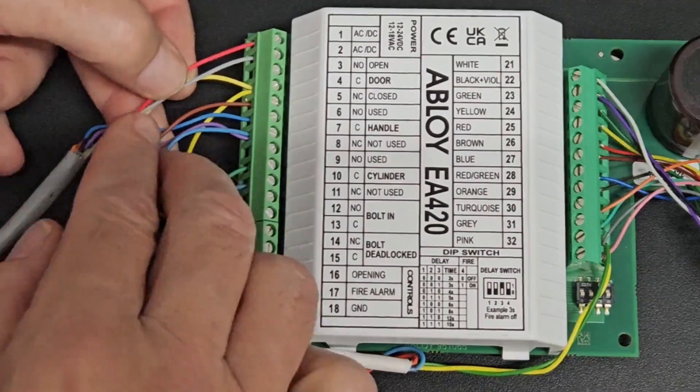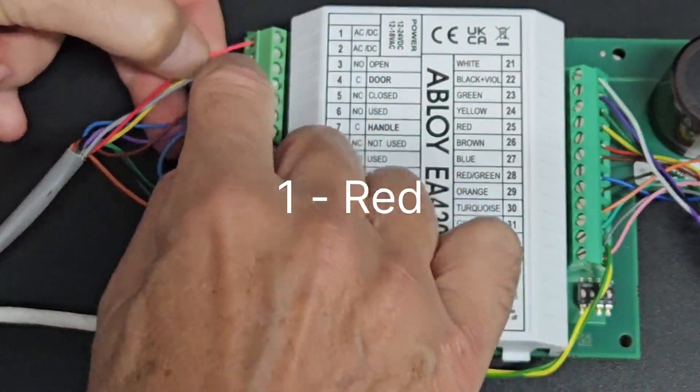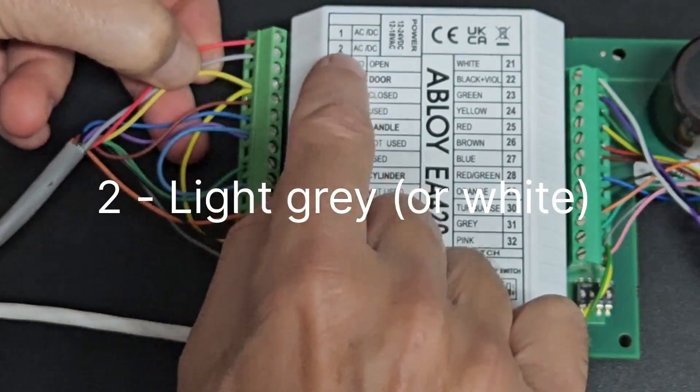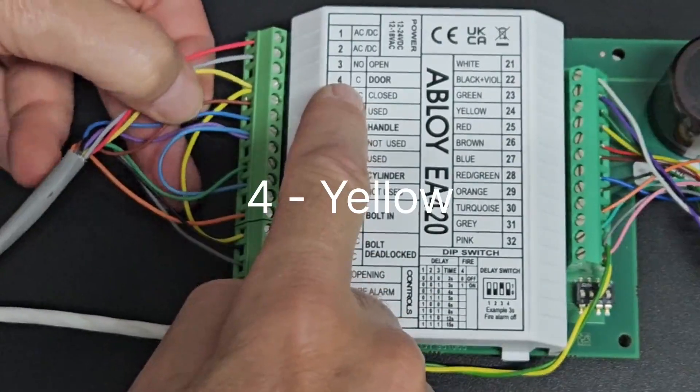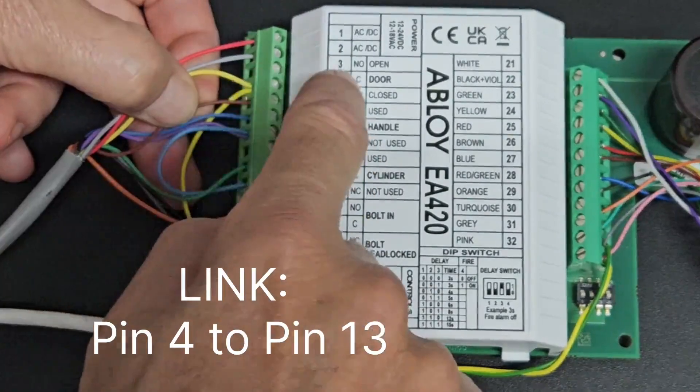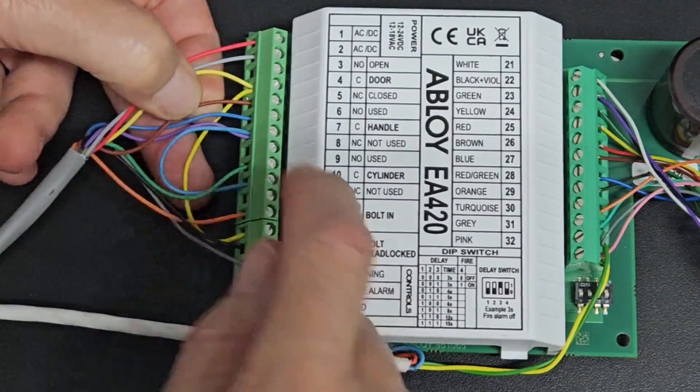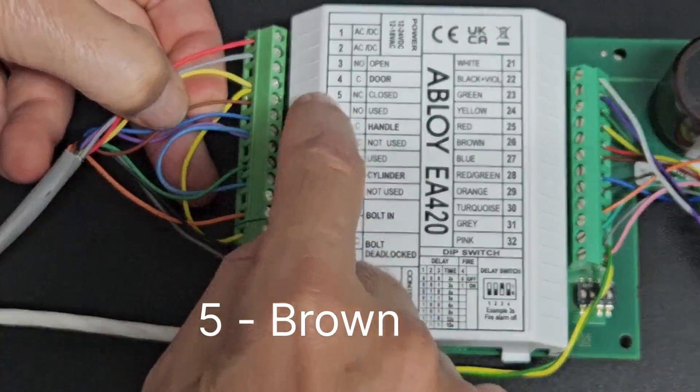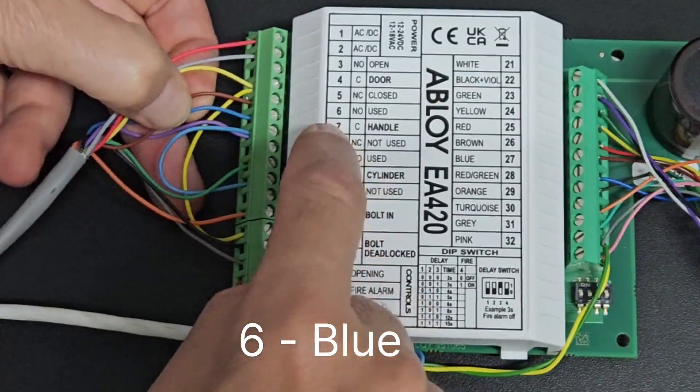Beginning with the 10-core cable, you fasten the red wire into number 1, the grey or the white wire into number 2, yellow wire into number 4, put a link from number 4 down to number 13, brown wire into number 5, number 6 is a blue wire.